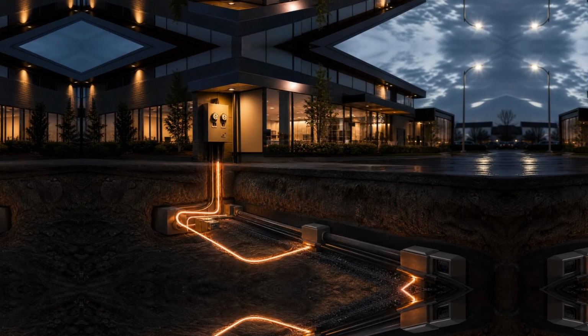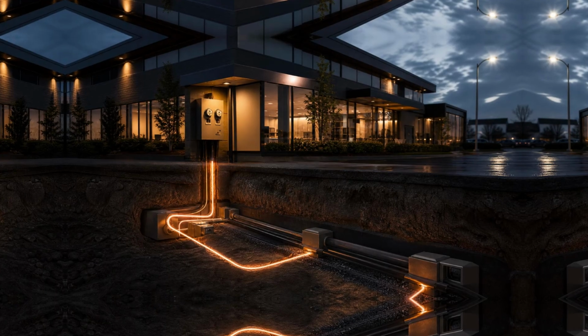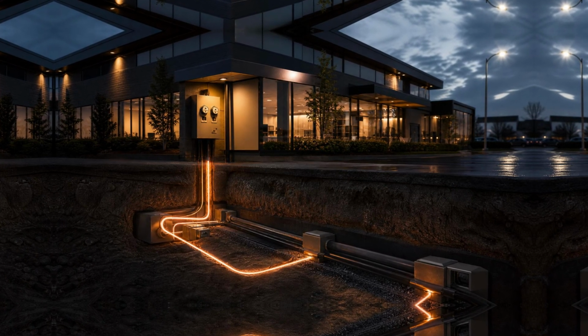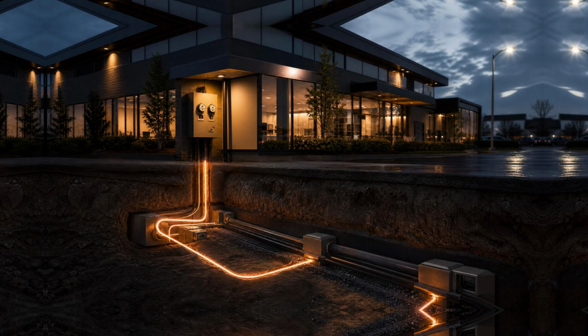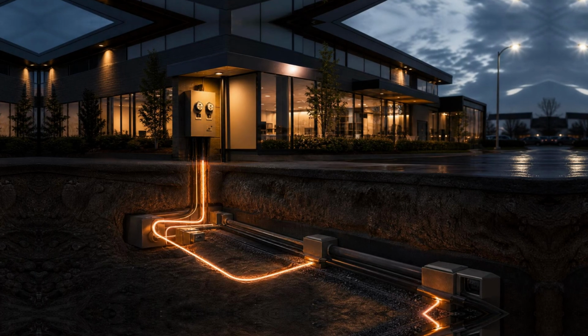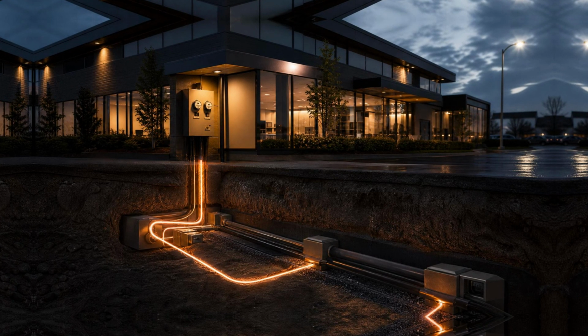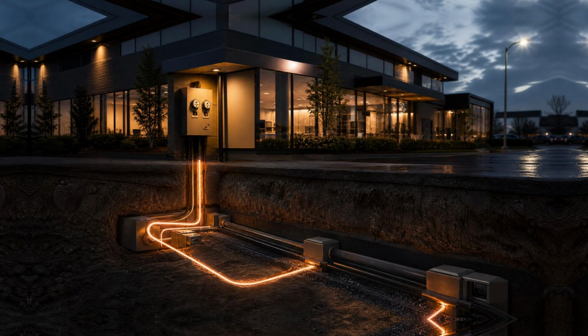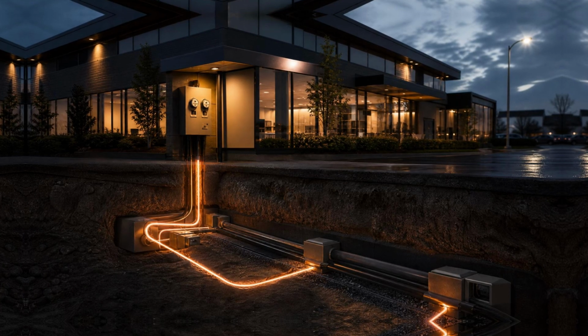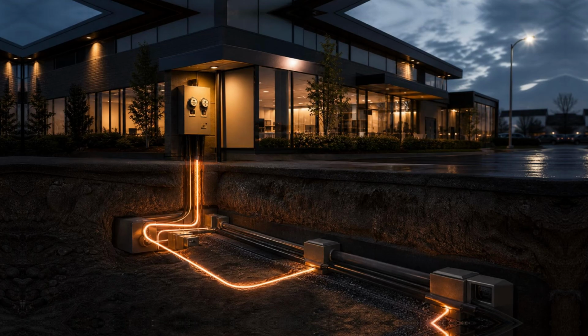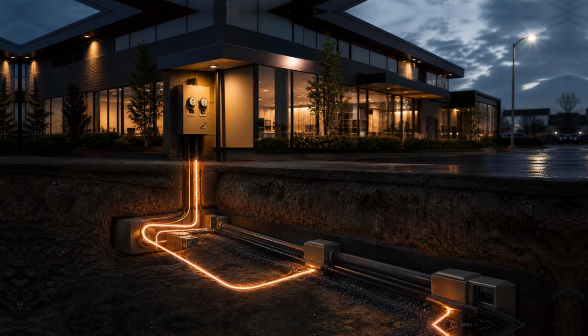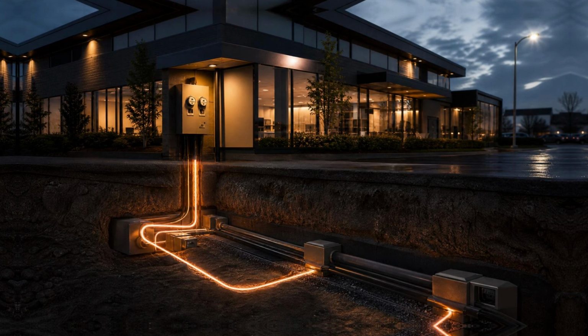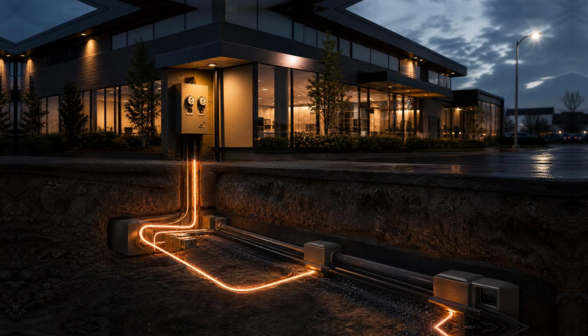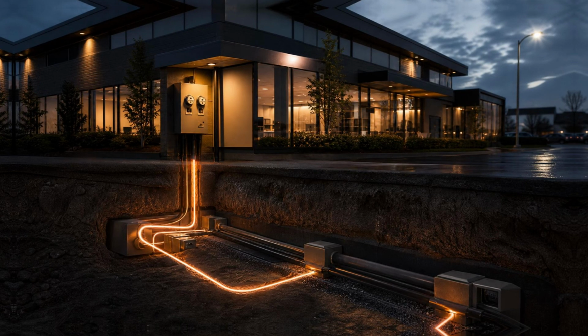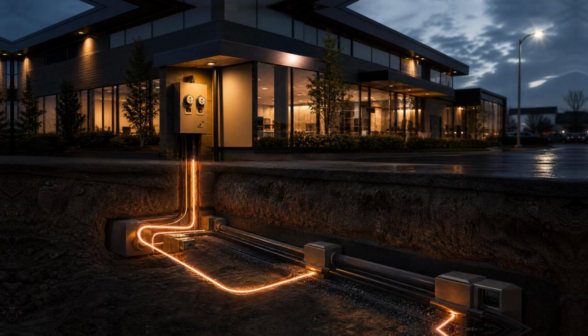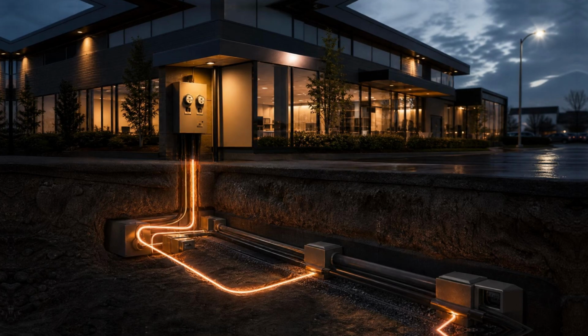What specifically is being watched? Voltage is one of the primary things. Voltage is the measure of electrical pressure, the force, in a sense, that pushes current through the building circuits. Normal commercial utility voltage arrives at a specific level, and it is expected to stay reasonably close to that level. If the voltage drops significantly below where it should be, the building's equipment may not function properly. Motors can labor, sensitive electronics can behave unpredictably, critical systems may begin to falter. A well-designed monitoring system notices a voltage drop early. It does not wait for the problem to become obvious. It watches the levels continuously, and when they drift outside the acceptable range, it takes note. Something has changed. Something may need to happen.